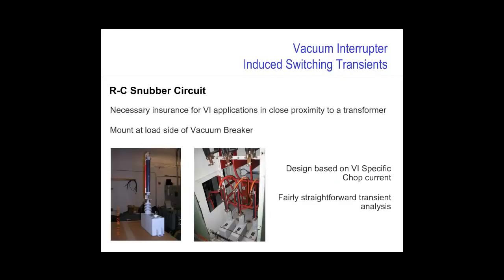For illustrative purposes, we've shown here the RC snubber network that was installed in this specific application. Again, the application of this VI really is only an issue when it's in close proximity to the transformer. It was actually mounted in the assembly as a part of the retrofit activity on the load side of the vacuum breaker. It was designed specifically to the chop current of the VI and the breaker itself, and via a transient analysis, the sizing of both the capacitor and resistor were fairly straightforward. Snubber design is obviously a technical subject unto itself, and we intend to take a look at this a little closer in a separate Lunch and Learn. But for now, let's push forward.